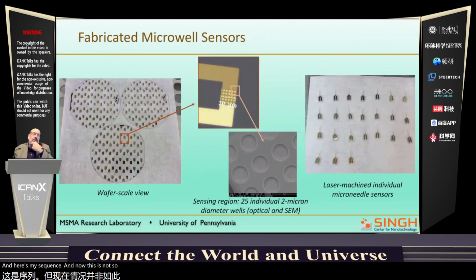All the way on the left, we use glass wafers for this, fused silica wafers. You can see a wafer scale view of the devices. If I zoom in on one of the devices, you can see the bottom gold and the top gold and the overlapping area with the microwells. If I zoom in on the microwells, you can see they typically consist of 25 individual wells that are 2 microns in diameter on the sensing region. Then I can individualize these using, instead of dicing, laser micromachining so I can get a needle shape with the sensor at the tip. The typical width of these needles is about 900 microns, and the length is about 4 millimeters, to give you an idea of the size.